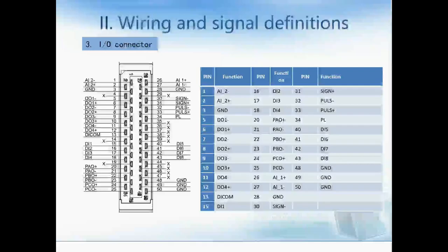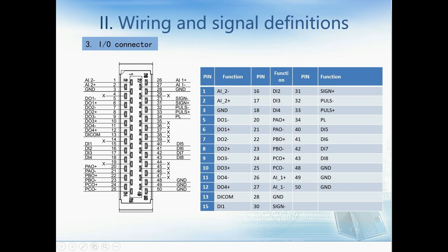This is the I/O connector, and this one is the encoder connector. Because it's a ready-made cable, we don't need to solder the pins ourselves — just make the connection. On the I/O connector, here we can see AI1 and AI2. AI1 and AI2 are for speed reference and torque reference. Both signals range from minus 10V to 10V.